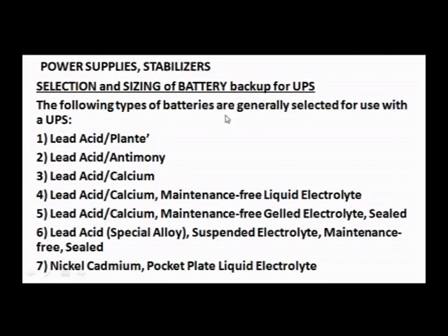The following types of batteries are generally selected for use with UPS. Please see how many different sets of batteries there are. You may only be knowing lead acid and nickel cadmium, but there are many subtypes too: lead acid plante, lead acid antimony, lead acid calcium, and lead acid calcium maintenance-free liquid electrolyte.